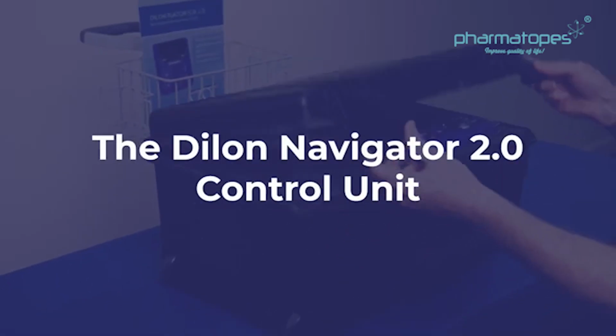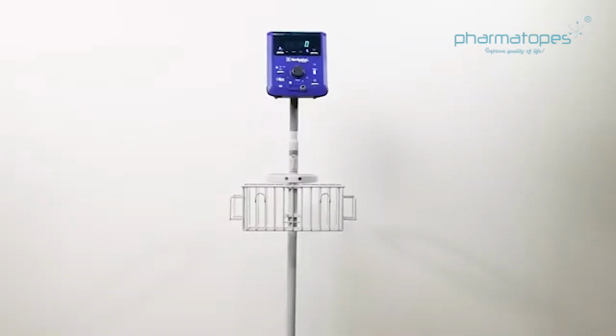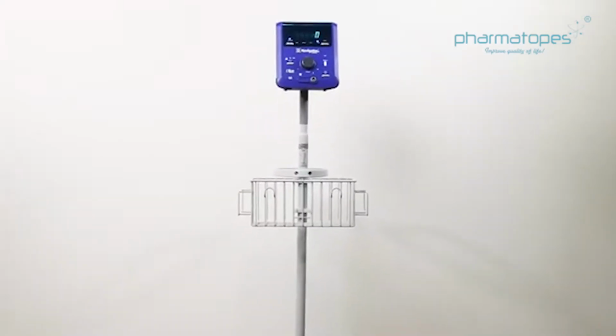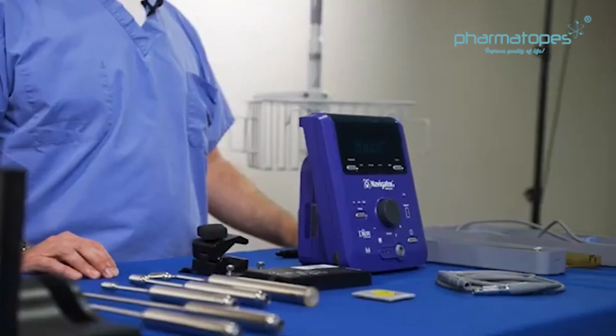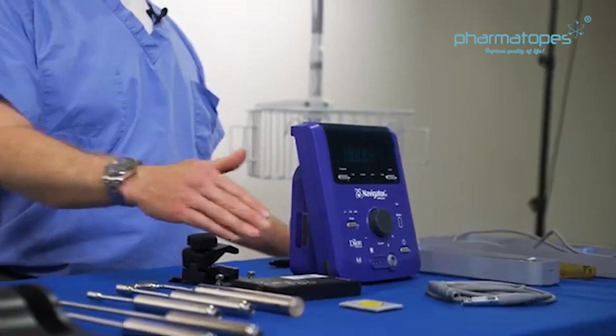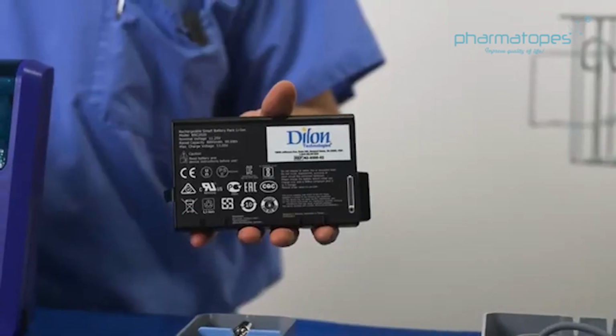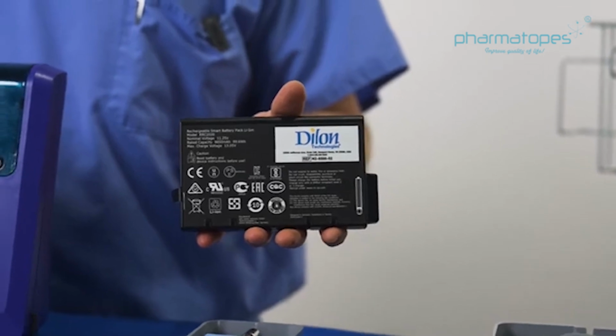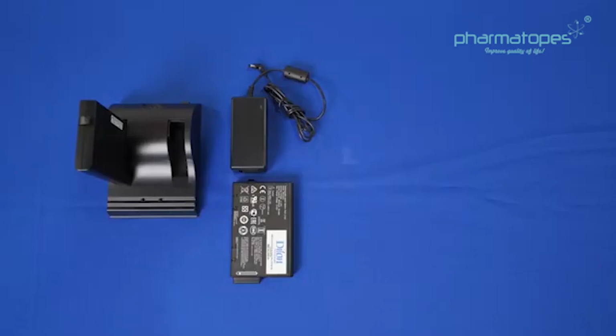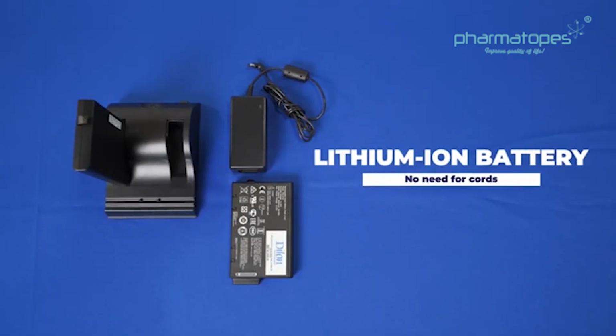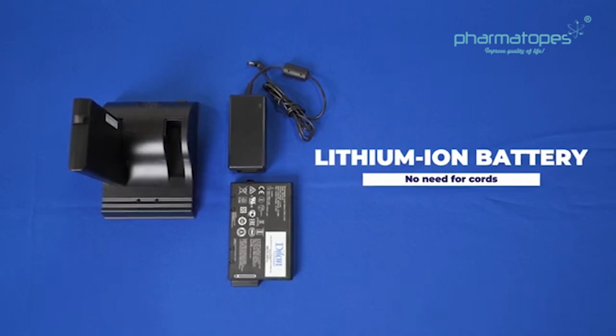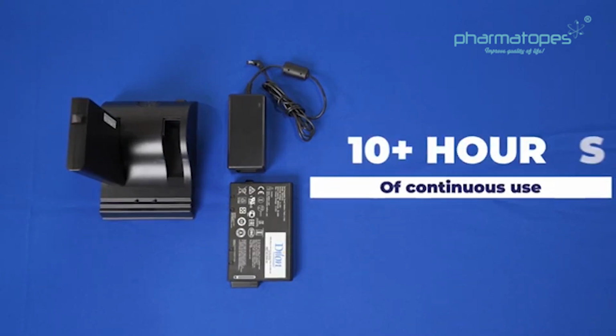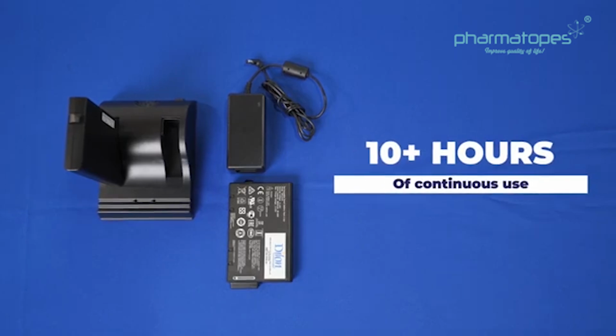The Navigator 2.0 control unit is rechargeable, cordless, and compact. It can attach to an IV pole or the Navigator rolling cart. First, you will need a fully charged lithium-ion control battery. Remember to always start a procedure with a fully charged battery. The battery mitigates the need of a power cord, which can add an unnecessary trip hazard in the operating room. A fully charged battery will provide over 10 hours of continuous use.